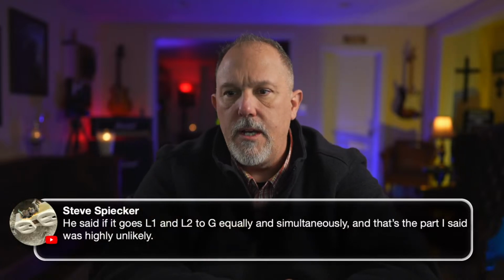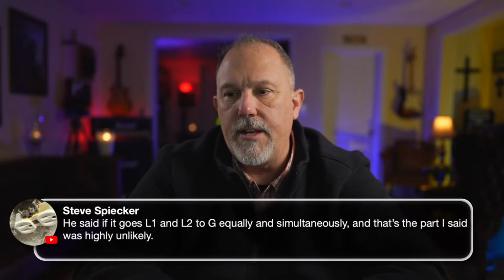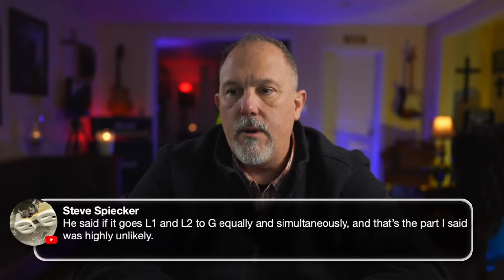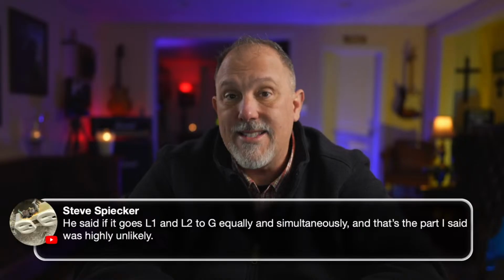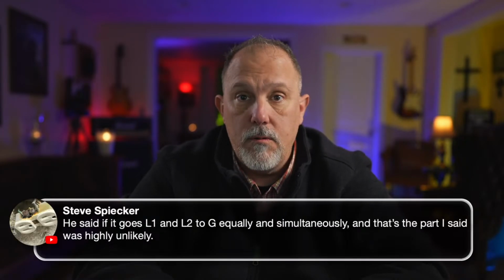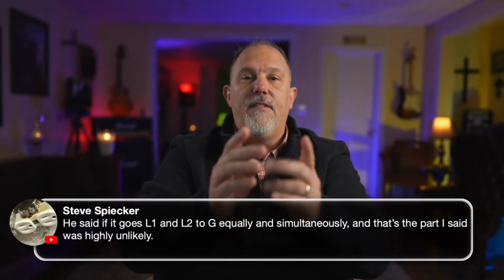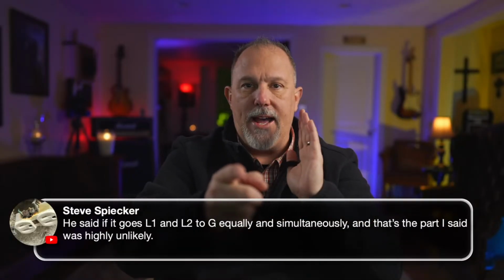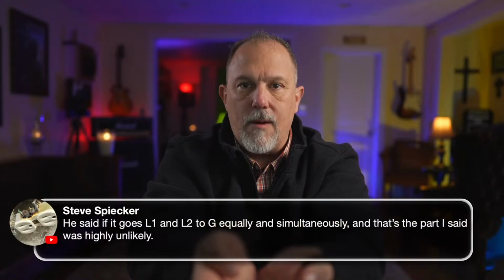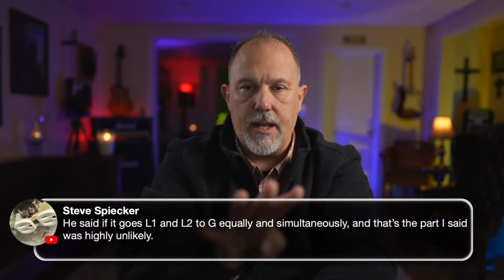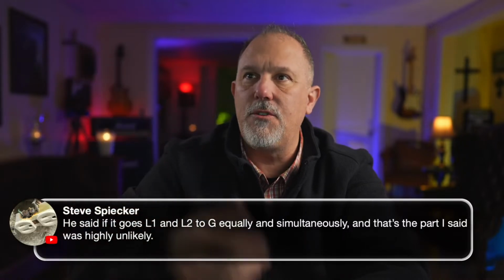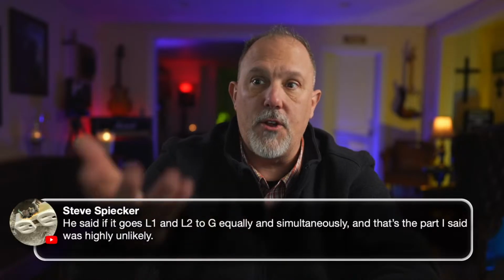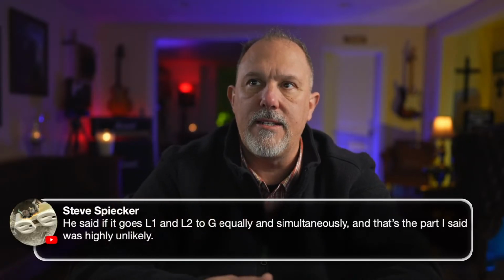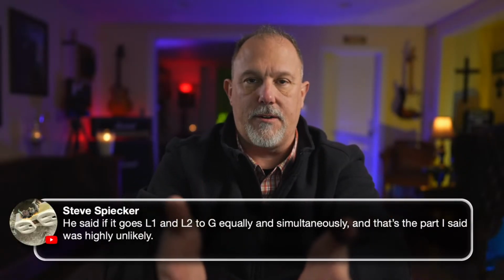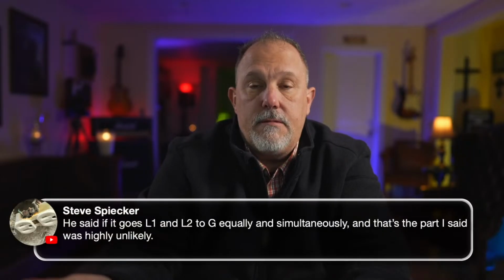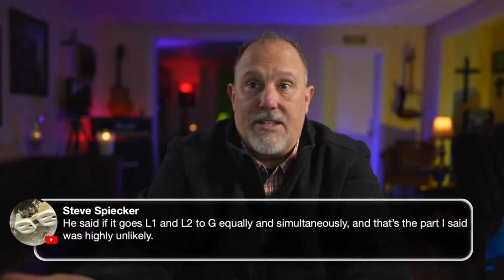Verify through test. He said if it goes L1 and L2 to ground equally and simultaneously. Well, if it goes to ground, Steve, it's outside of the path, even if it's equal. L1 and L2, if I have 30 amps going out, 30 amps coming back, and both of those leak to ground 2 milliamps, that's 4 milliamps. Or say, I can't say 2 milliamps. It says 2 milliamps each. That's 4 milliamps. Still not enough to trip a GFCI. Say it was 6 milliamps each, and I had 12 milliamps of leakage current. I've got 12 milliamps of leakage current. So it's going to trip.